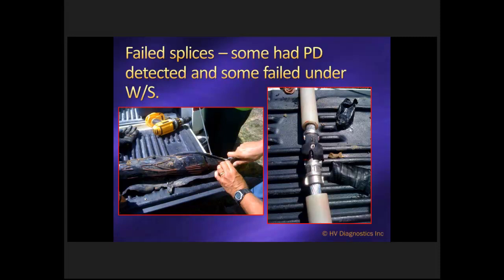The withstand caught some of the defects, while the PD caught some others. So the combination of the withstand with the PD is a very, very good thing to do. And by the way, that's also what cable manufacturers have to do. They have to do a PD test and a withstand test on a cable.